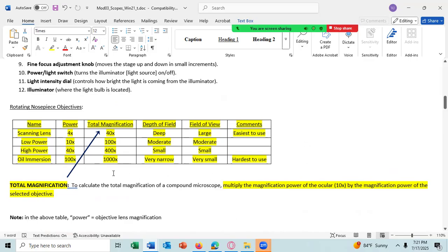With the 4X lens being used, you should have the iris diaphragm open, almost all the way, maybe not all the way. But actually for Köhler illumination, you want the objective to give you a cone of light equal to the size of your field of view under the objective lens.